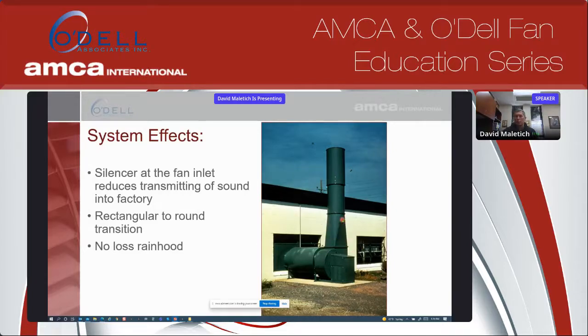Discharge, we have a rectangular to round transition, a round piece of duct, and we have a no-loss rain hood here. No losses associated with air movement through the duct. However, when the fan's off, rain comes down. Rain never comes at a straight vertical. It always comes at an angle, hits the side, and drops out on the outside of this duct here.